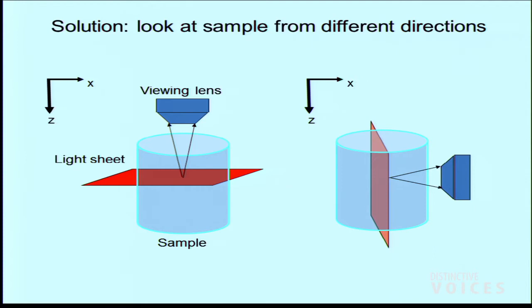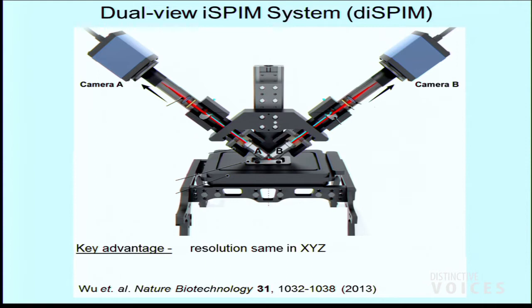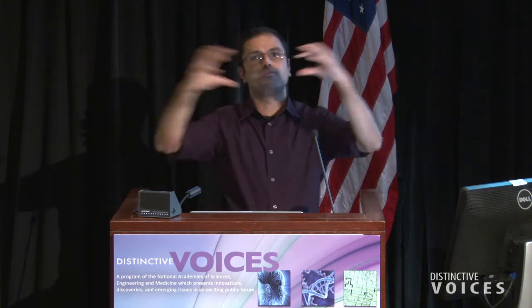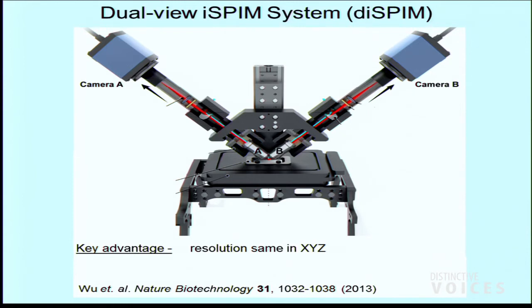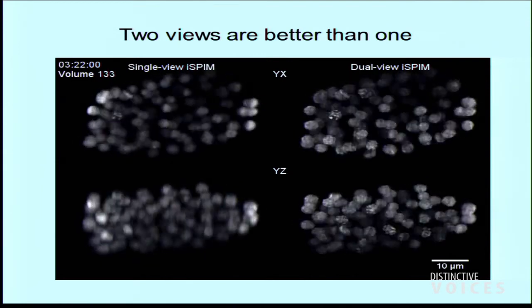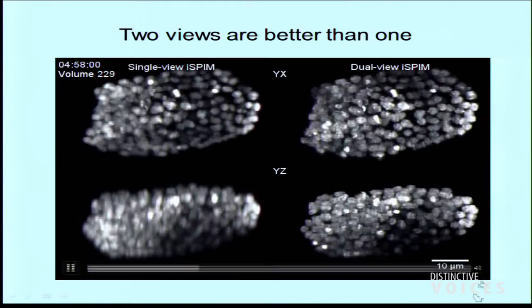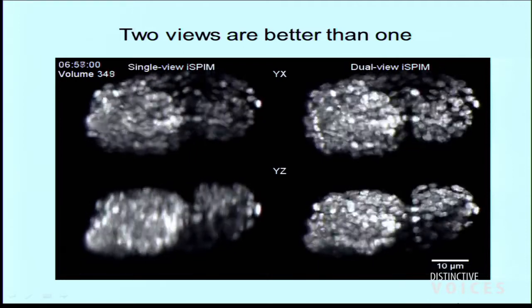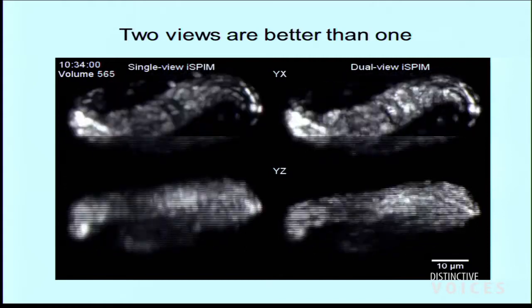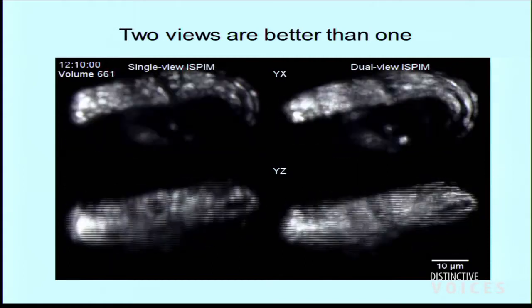If I take this coffee cup and look at it from one side, I get a good view but almost no information about depth. If I rotate it 90 degrees, I have a much better sense of the overall shape. The same is true microscopically — looking from two perpendicular directions lets me infer a lot more detail. We can use that idea in the context of this developing worm embryo. We take our iSPIM and just add a second camera. One objective brings in the light sheet, the other looks at it; then they swap roles. By fusing both data sets together using mathematics, we recover a data set with so-called isotropic resolution — the neurons look equally good no matter how we look at the volume. We're only taking twice as many images, the embryos all still hatch on time, and we're not compromising the phototoxicity advantage.